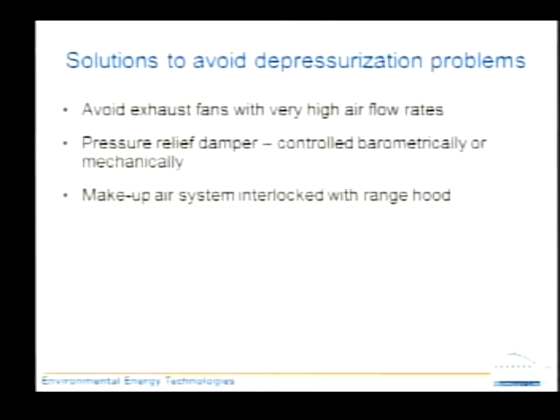But people have the model in their mind of an airtight home. So you've got to be really, really careful of what you emit into an airtight home because there's not a lot of ventilation. So I want to be really careful about not backdrafting or spilling pollutants into that home, okay? But if it's taking 700 CFM to pull pollutants in, then that's not an airtight home anymore. That's a 700 CFM wind tunnel, okay? Again, the contrast is you turn on your cooking burner, you're spilling those pollutants, all those pollutants are coming into your house without any extra ventilation.